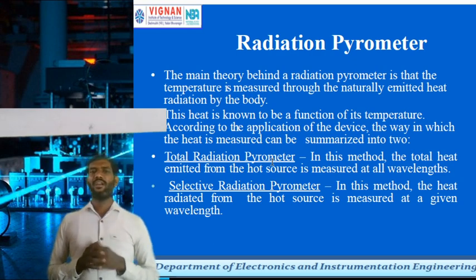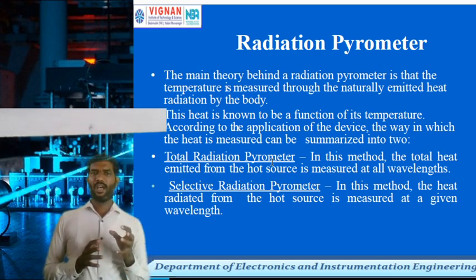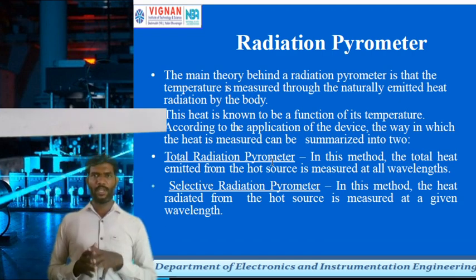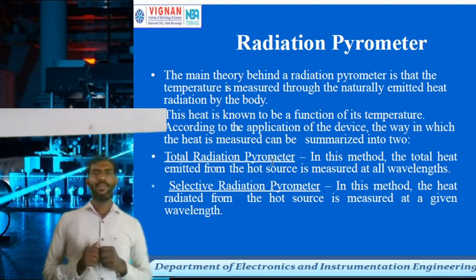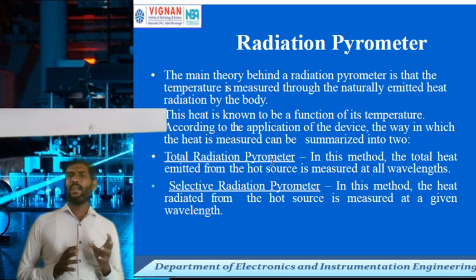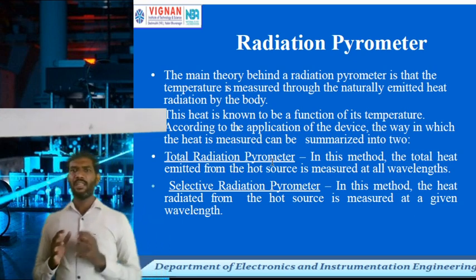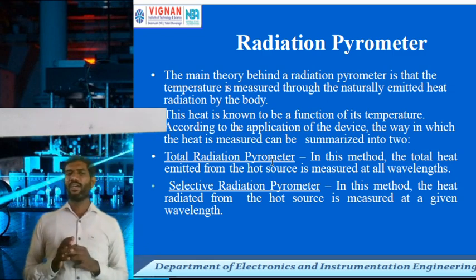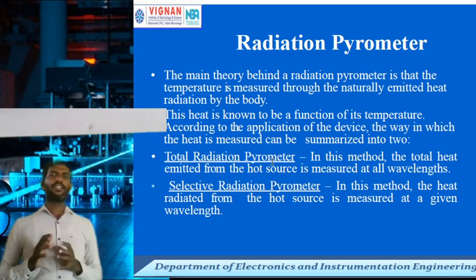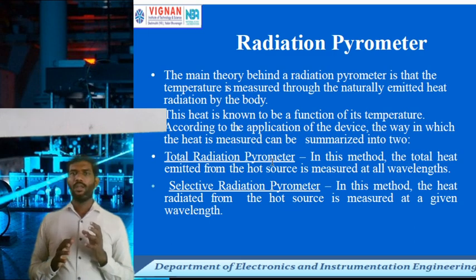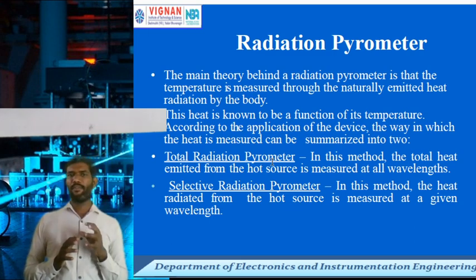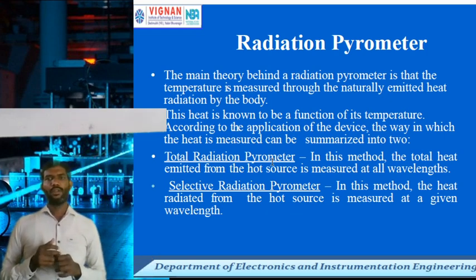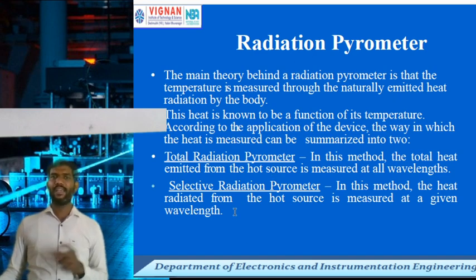Next is the radiation pyrometer, which is very important and also used in blast furnace temperature measurement. The radiation pyrometer measures temperature through the naturally emitted heat radiation by the body, where heat is a function of temperature. According to the application, the way heat is measured can be summarized into two methods: total radiation power pyrometer and selective radiation pyrometer. The total radiation pyrometer measures all heat emitted from the heated source at all wavelengths, whereas the selective radiation pyrometer measures heat from the source at a given wavelength.